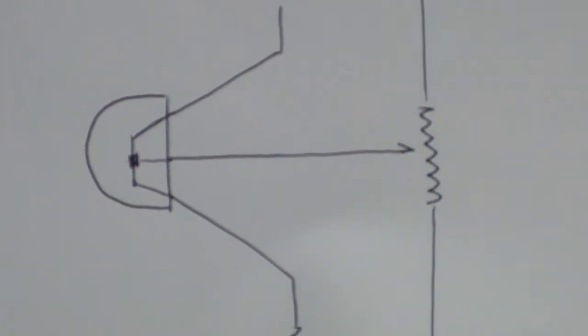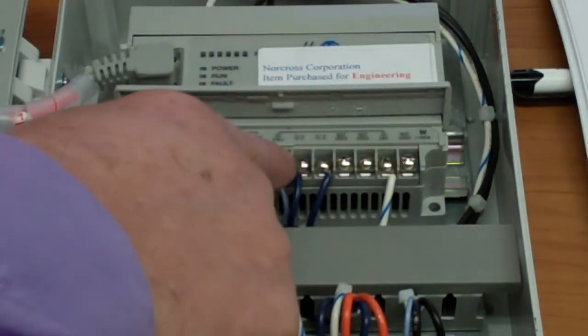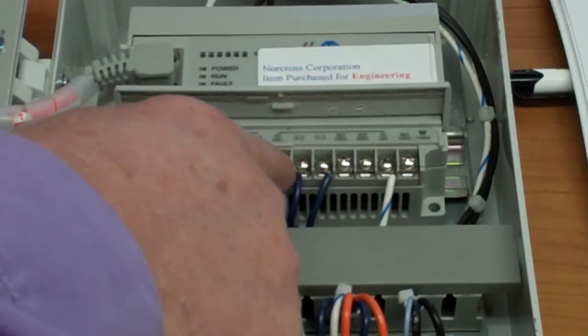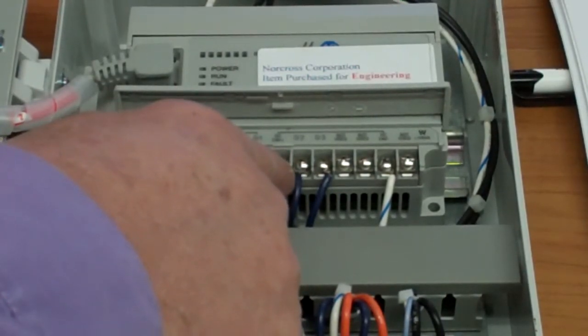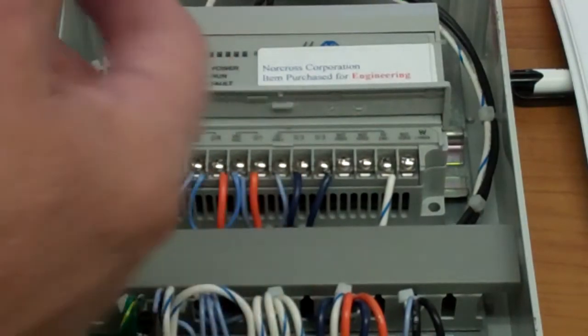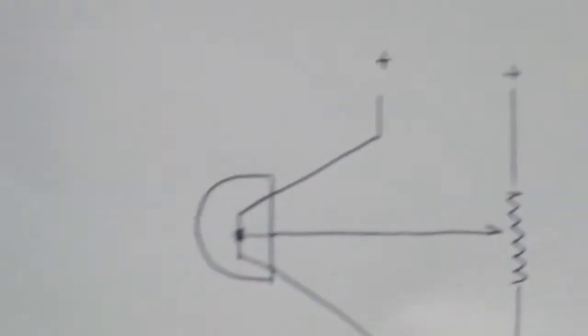...turns off. So aside from just FETs leaking and failing and being damaged by voltage spikes - and valves cause inductive voltage spikes - you can also have the basic leakage current causing relays to not drop out unless you size things right.